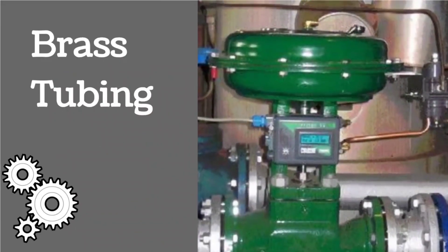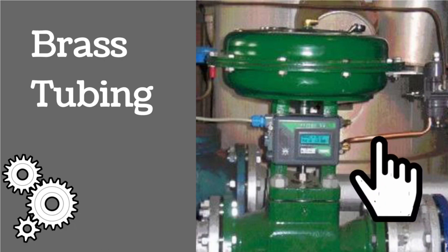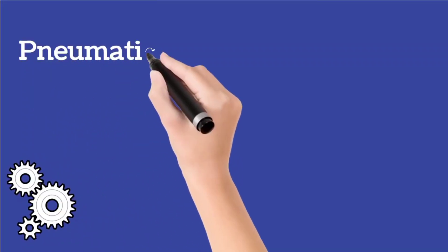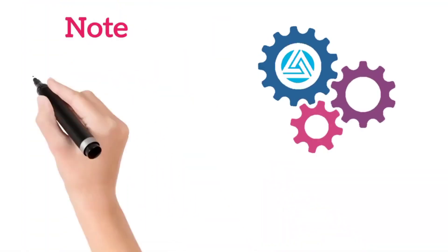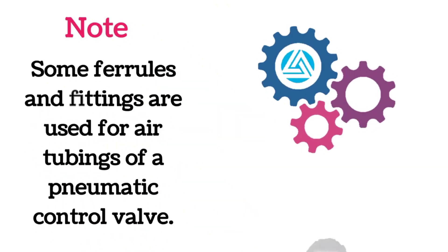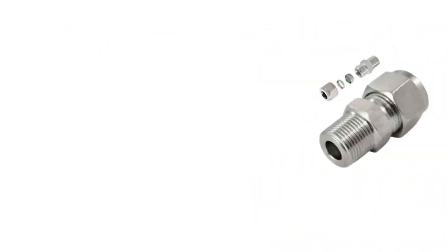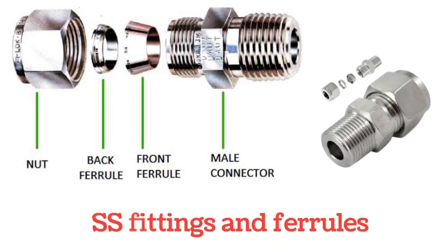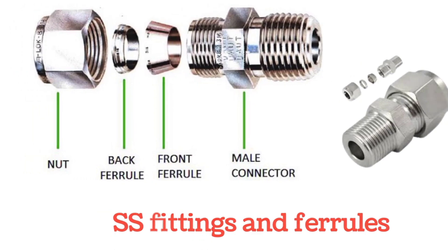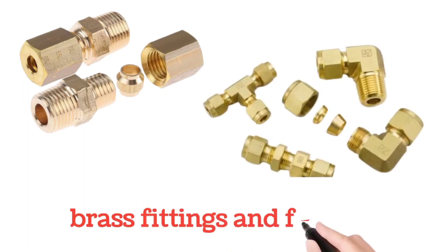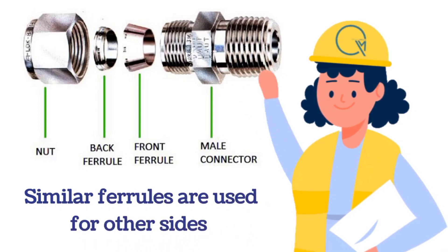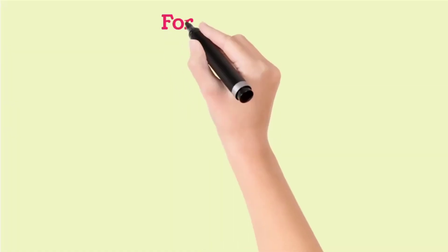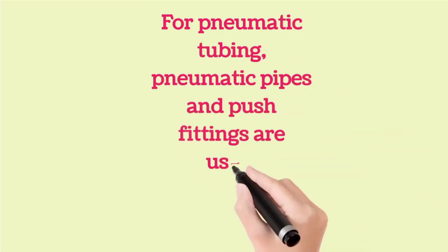The third type of tubing is pneumatic tubing, shown by the arrow. Note that some ferrules and fittings are used for air tubing of a pneumatic control valve. SS ferrules and fittings are shown in the images, along with various parts of the fitting and ferrule. Brass ferrules and fittings are also shown. An important point: similar ferrules are used for both sides of the connector. For pneumatic tubing, pneumatic pipes and push fittings are used, as shown in the images.